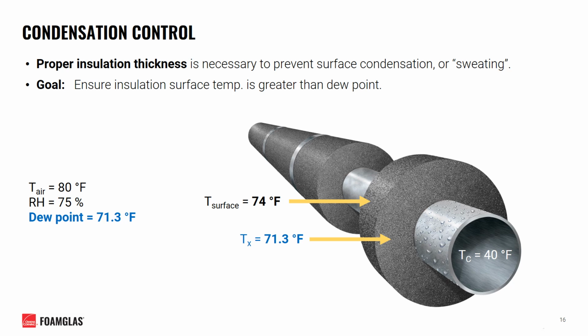I mentioned it briefly just there, but surface temperature of your insulation actually plays a pivotal role in proper condensation control as well. Proper insulation thickness is necessary to prevent surface condensation or sweating from occurring. Our goal should always be to ensure that the insulation surface temperature is greater than the surrounding air's dew point. Below you can see we have a chilled water pipe of 40 degrees Fahrenheit with ambient air of 80 degrees and relative humidity of 75%, giving us a dew point of 71.3 degrees. In this example, we make sure to use enough insulation thickness to achieve a surface temperature of 74 degrees, safely preventing surface condensation from occurring on our insulation.